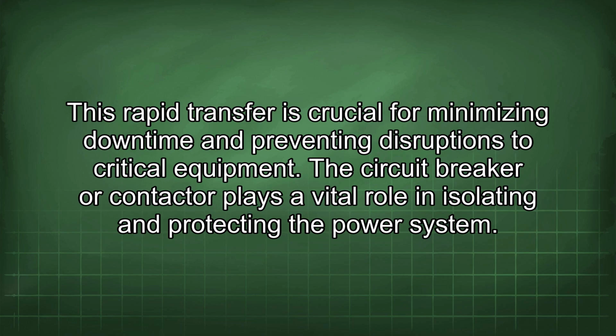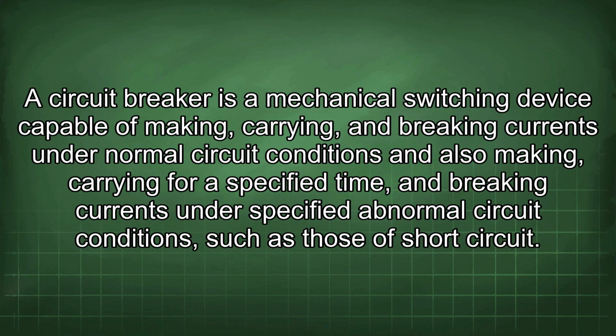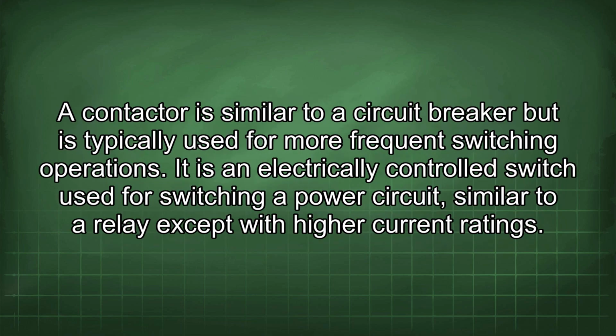The circuit breaker or contactor plays a vital role in isolating and protecting the power system. A circuit breaker is a mechanical switching device capable of making, carrying, and breaking currents under normal circuit conditions, and also making, carrying for a specified time, and breaking currents under specified abnormal circuit conditions, such as those of short circuit. A contactor is similar to a circuit breaker but is typically used for more frequent switching operations.